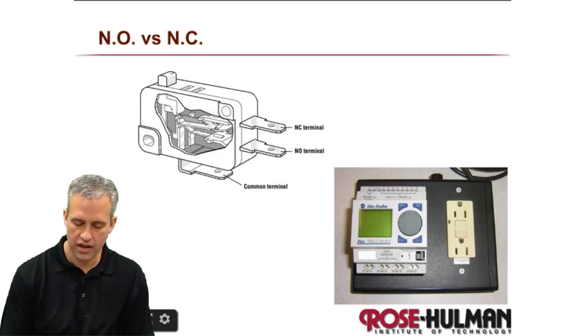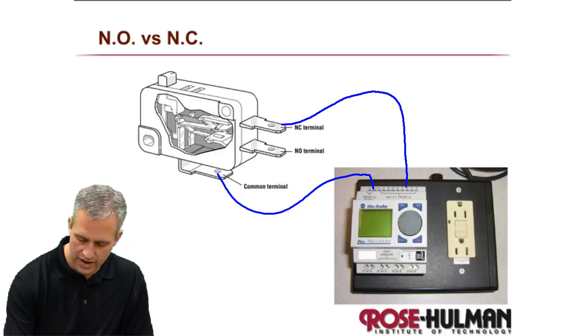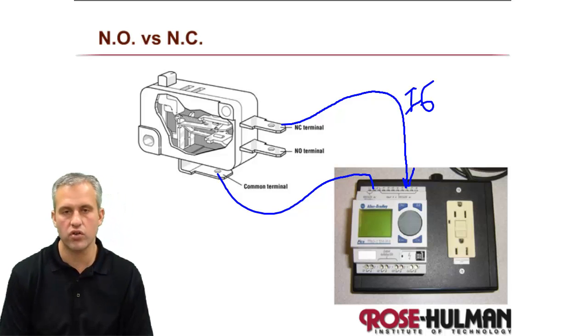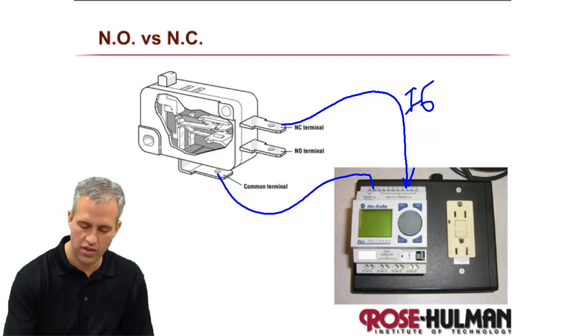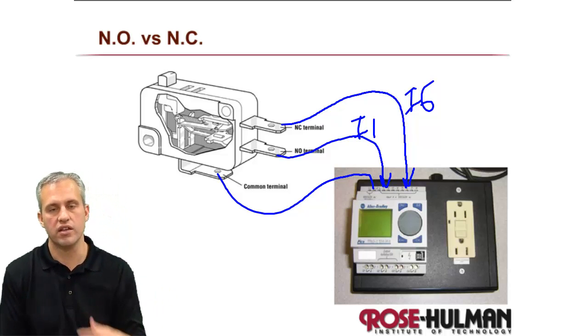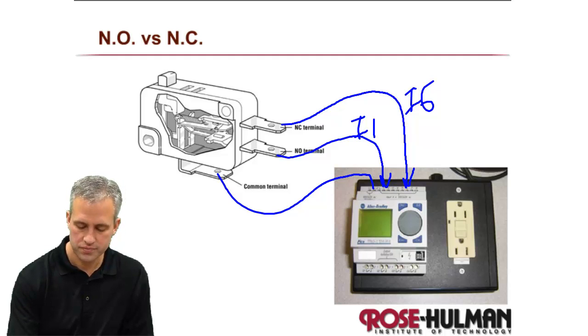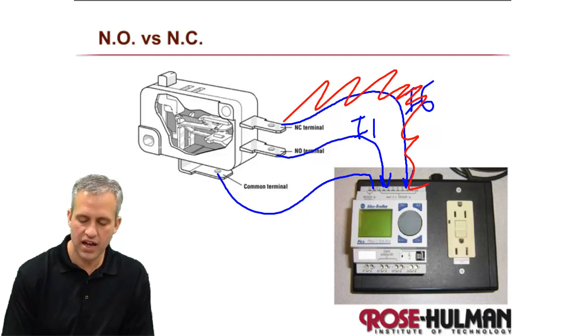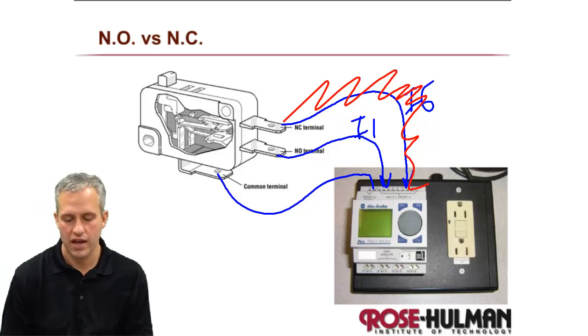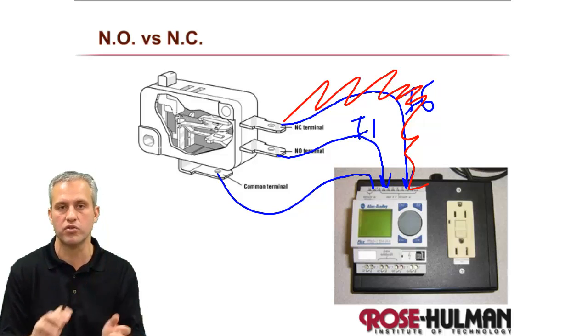For example, if this switch is connected to the common line and going to input I6 on the normally closed line, you have to know that. And if it's going to I1 on the normally open line, you have to know that too. Typically you'd only connect one or the other. If the person who built your system is being nice, they'll connect normally open, but they may connect normally closed and you have to be able to adjust.